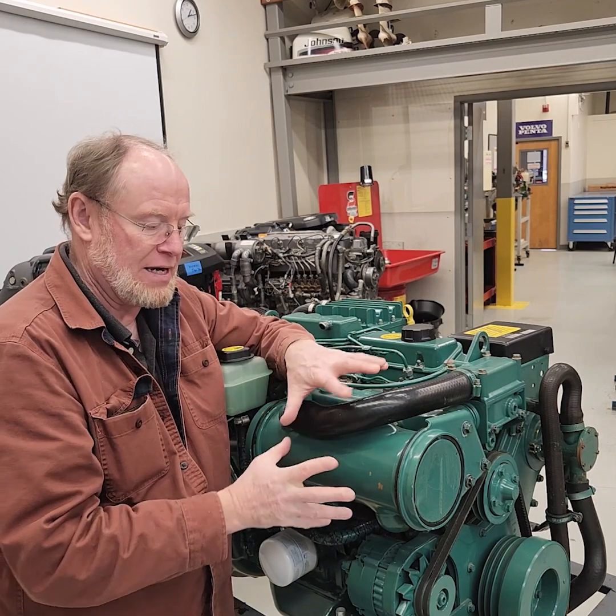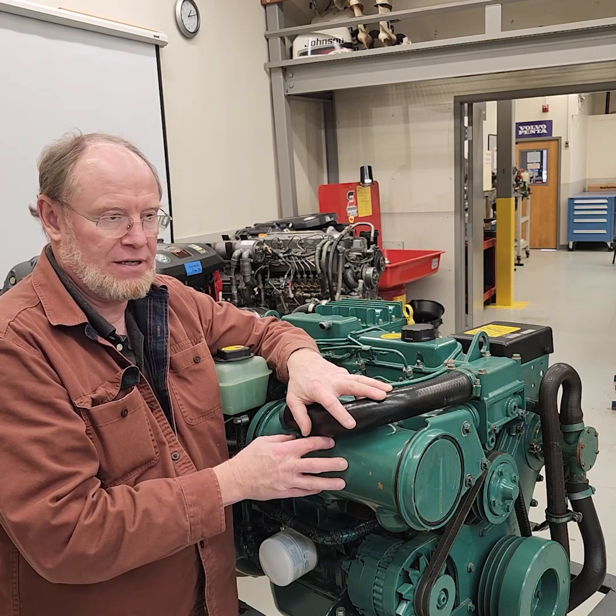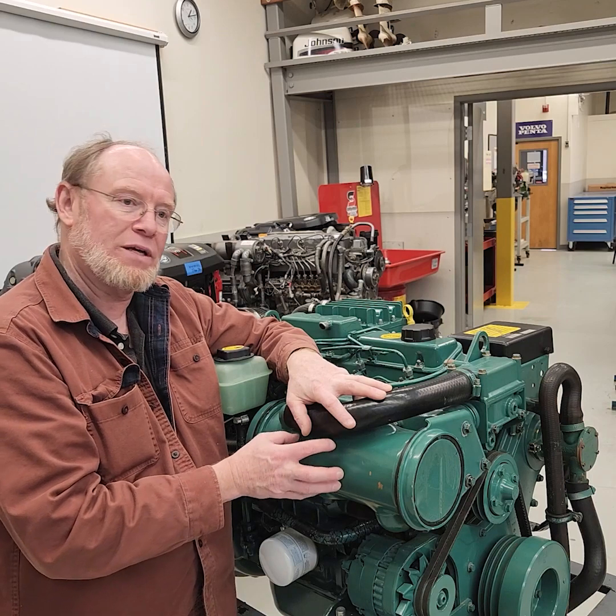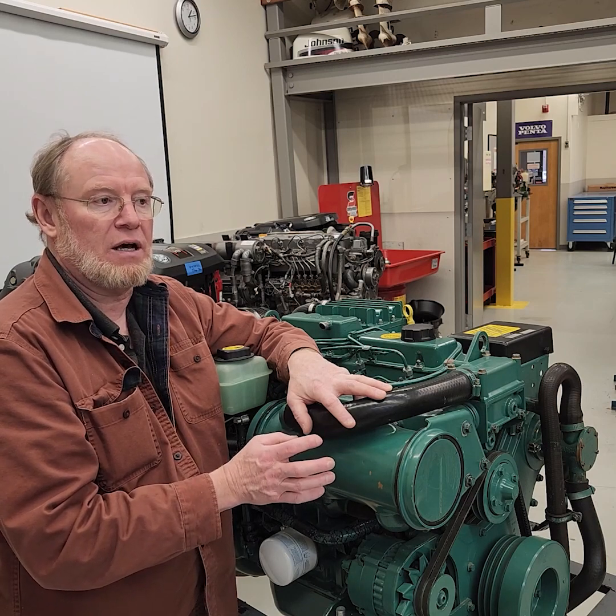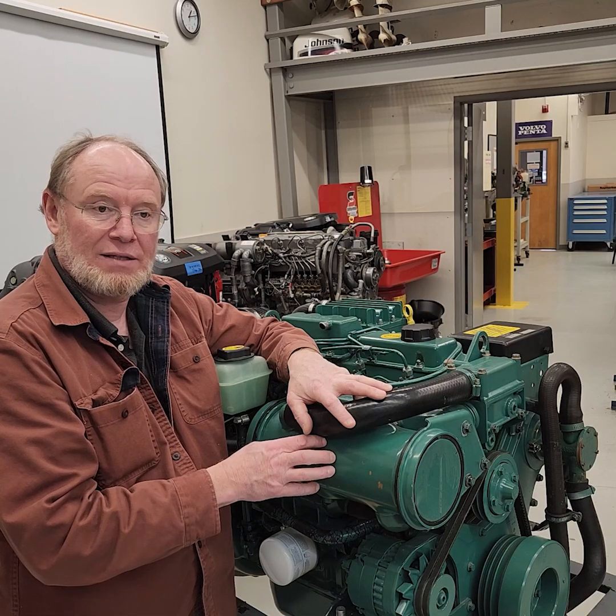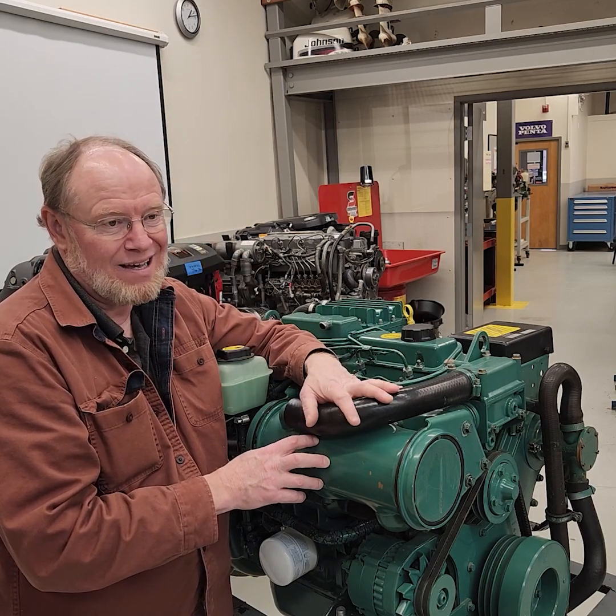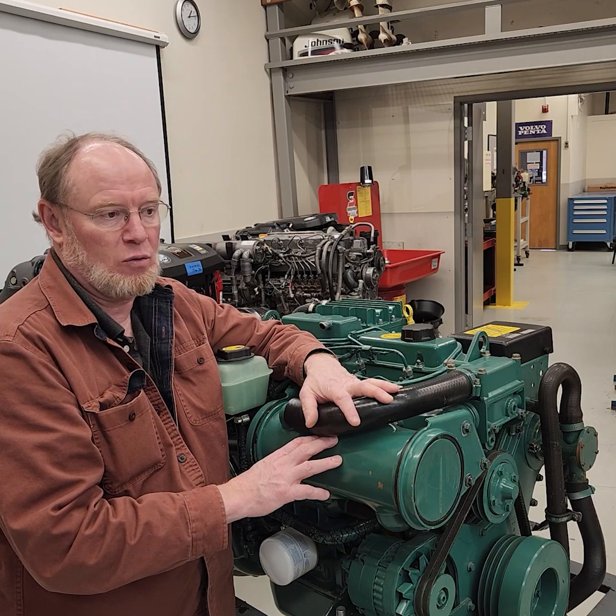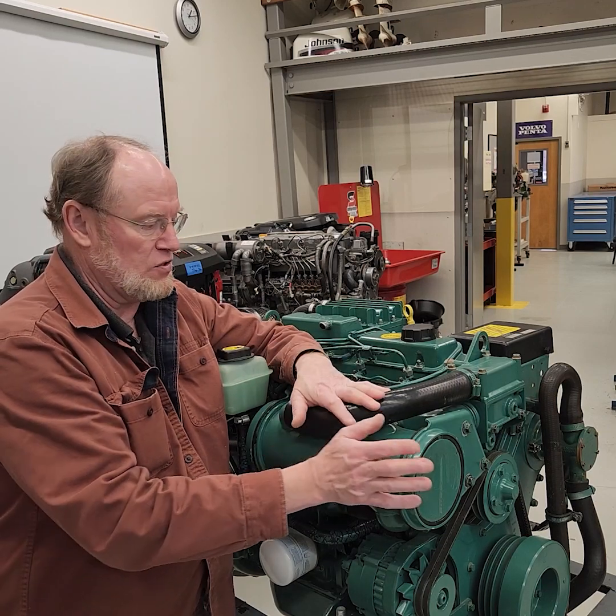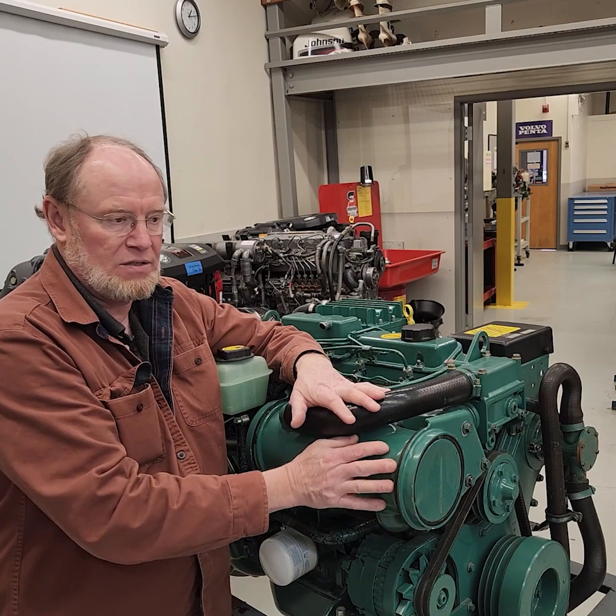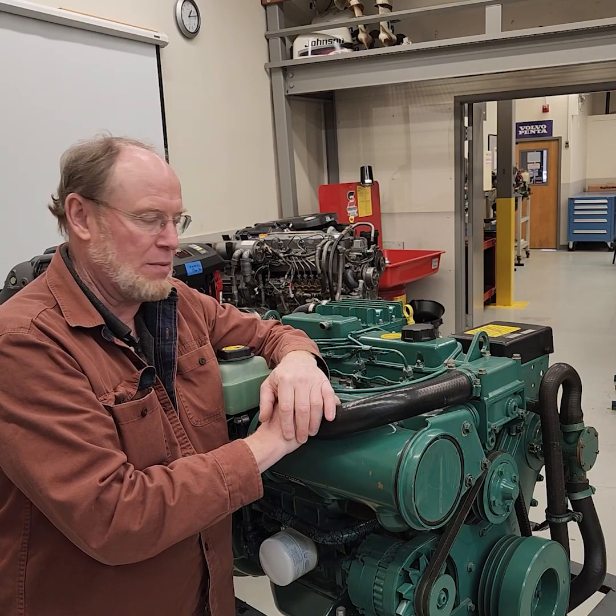Well, I hope this helps you understand how to backfit the anodes into an older. These are from the 90s. They are the TAMD 30 series engines. I'm not positive a 42 series or a 41 series uses this type of system with this heat exchanger. But I know that the TAMD 30 series ones came with drains, not anodes. The EDC engines, the TAMD 44 or KMD 44, the TAMD 74s, any of the EDC engines, the first generation electronic control engines, all have anodes in them. It's just these for some reason at that era that some of these engines, they put drains in instead of anodes. So if you want to backfit it, easy enough to do. Hopefully that helps you with this little tip and I'll see you in the next video.